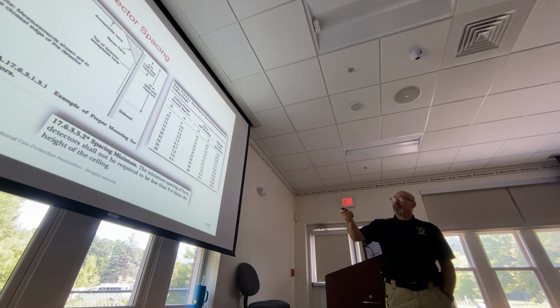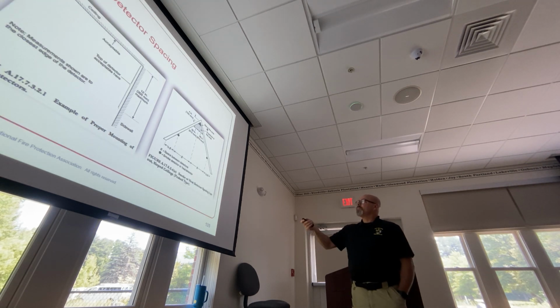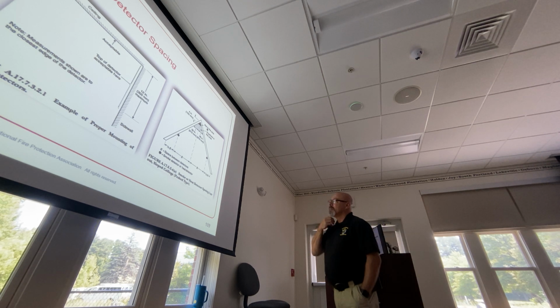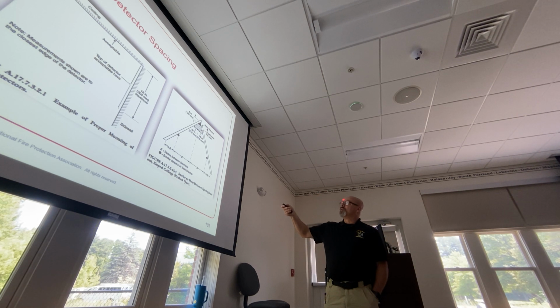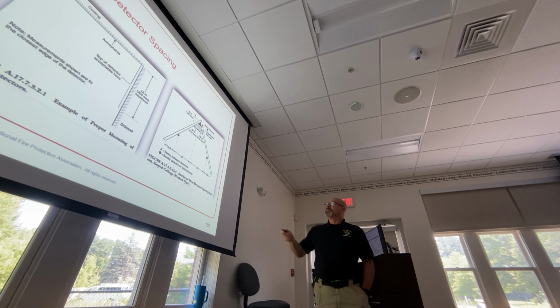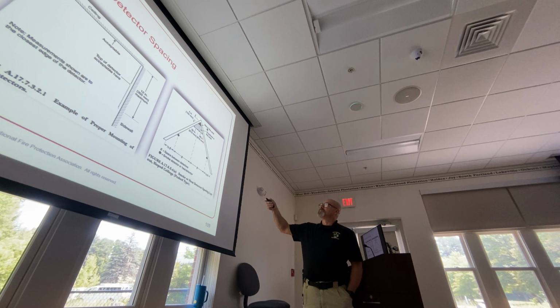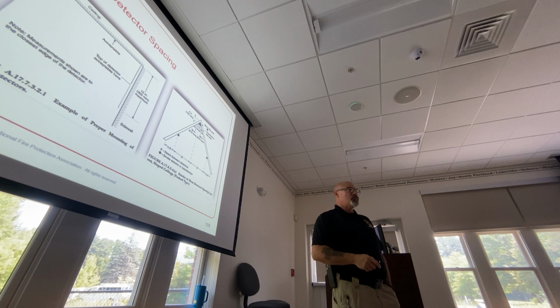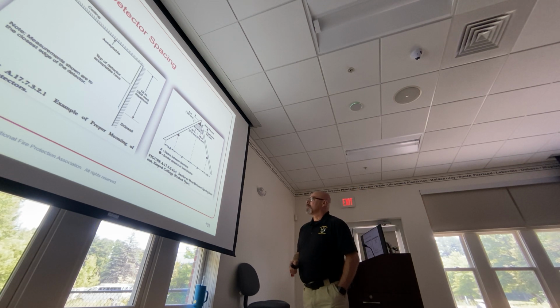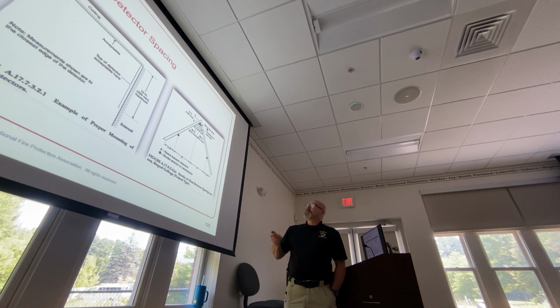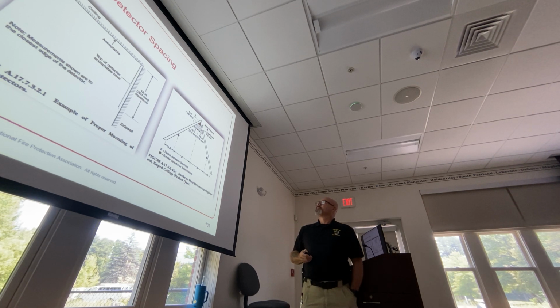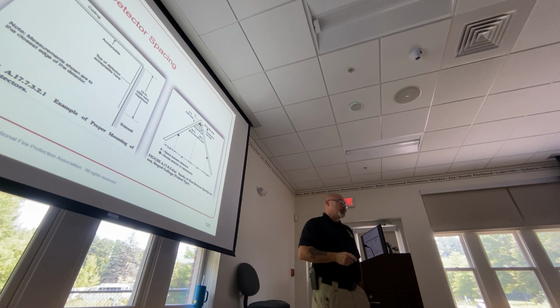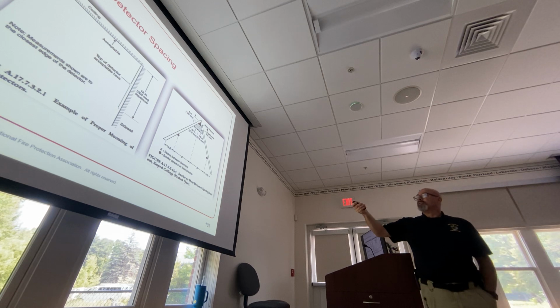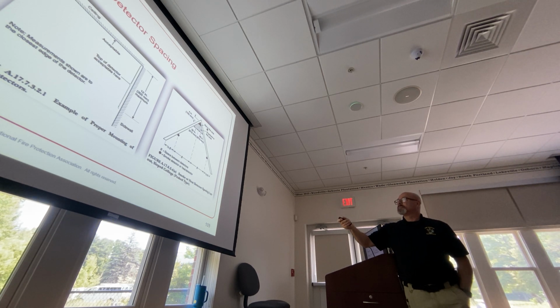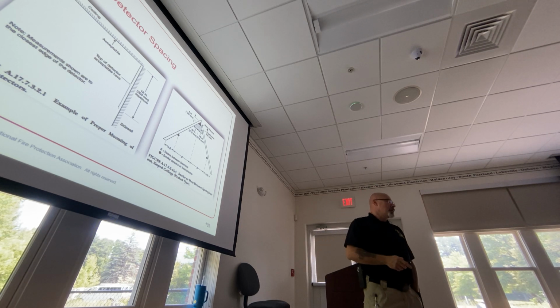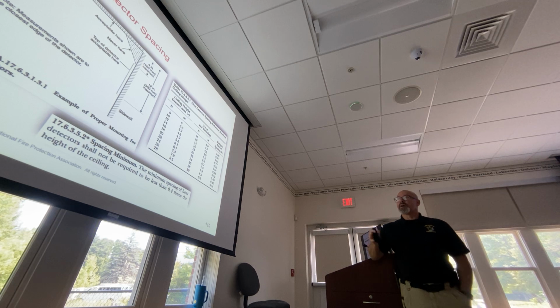inches down and 4 inches away. If you have a peaked ceiling, slope ceiling, it's telling you anywhere in this area is okay, but not up here. Again, because smoke's gonna come up and it's gonna roll. It's not necessarily gonna build right in that first 4-inch triangle of the peak. The question may be, in a peak slope ceiling, how far down is it acceptable to put that detector? 4 inches down, 36 inches across. Okay? All you have to do is just read the chart, read the question.